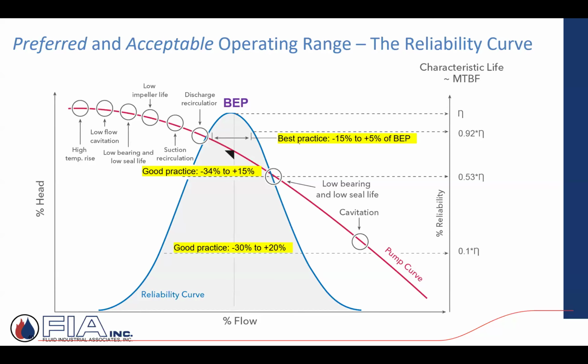The preferred and the acceptable operating range. So the POR and the AOR operating ranges. And what's happening is they say, hey, I've got this range, BEP is here, and I can move a little bit to the left of it or a little bit to the right of it, and I'm okay. But if I get extreme and start moving past that percentage, I can really damage the pump. I'm going to be very unhappy. The building owner, whoever bought this pump, is not going to be happy with the performance or the life cycle, the frequency of service, bearings, seals, etc. So best practice and good practice, like preferred versus acceptable. But you typically don't want to go past either the best or, at the worst case, the good practice.